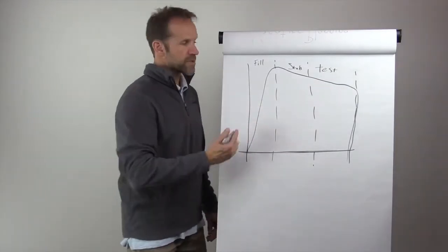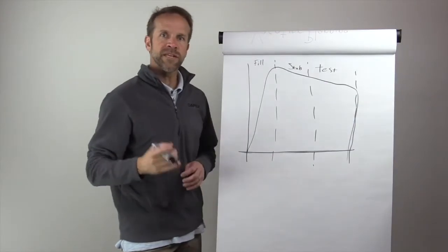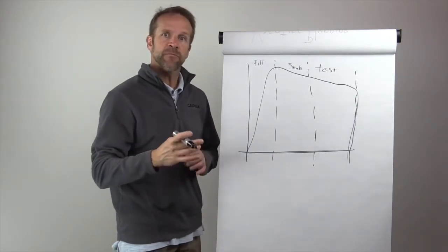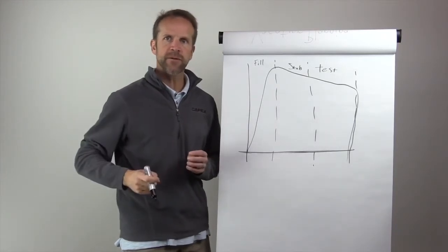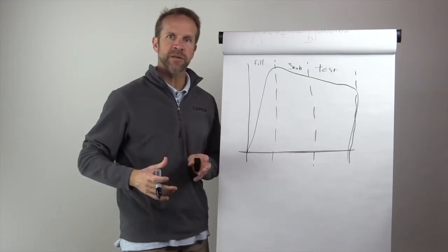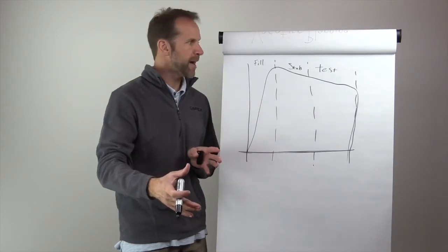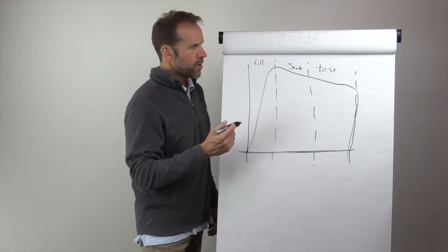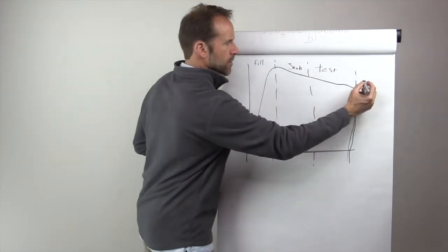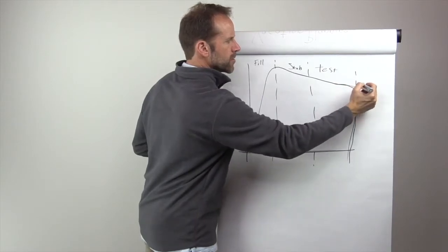With pressure decay, of course, we're losing pressure over time. So what we're doing is pressurizing the part, and then isolating the part. Theoretically, you could disconnect the air pressure from the leak test instrument, and it's still going to test on the circuit that we've pressurized. So that's pressure decay leak testing. When we do this, this is our known good part.